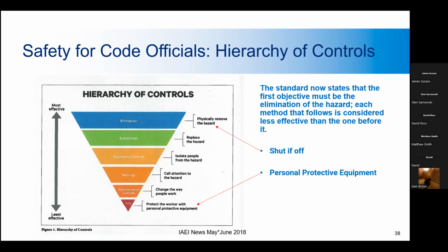Because of this, many municipalities have gone to visual inspections only, with no opening of junction boxes or electrical panels, and this is why. It prevents people from being exposed to those hazards. This is another reason that photos are required during the installation, because it allows you to see inside some of these things while they're being installed and before they're energized, which reduces the risk to the inspectors, who are typically not licensed electricians, right? So that's one of the main reasons NYSERDA requires photos during these inspections.